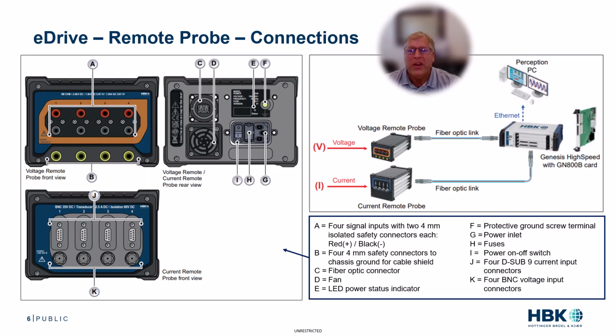Well, after making all the cable connections, including the voltage or current signals to the front end of both remote probes, the AC power cord and fiber optic cable on the rear of both remote probes, and all the appropriate connections on the mainframe, it's now time to turn on the power switch on the remote probes, followed by the power switch on the Genesis Power Analyzer mainframe. And you'll need to wait about 5 minutes for the remote probes to warm up and establish communication with the mainframe.